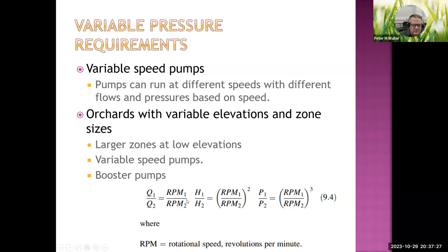The affinity laws for variable speed pumps: flow rate is directly proportional to the speed ratio, head is proportional to the square of the speed ratio, and power is proportional to the cube of the speed ratio.